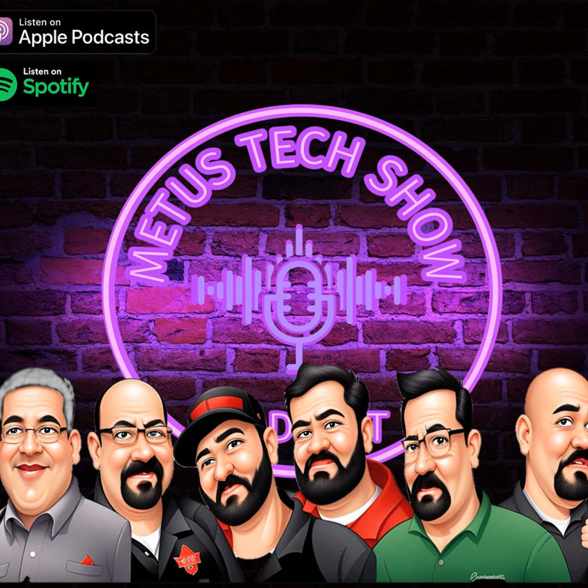Thanks, Paul. This week's METUS Minute is on solenoid valves. A solenoid valve is an electronically controlled device that acts as an on or off switch for refrigerant flow. They are crucial for controlling refrigerant flow in various stages of the HVAC cycle, including cooling, defrosting, and preventing refrigerant migration. A solenoid valve consists of a coil of wire, the solenoid, that when energized with electricity creates a magnetic field. This magnetic field attracts a movable core, either a plunger or an armature. The movement of the plunger opens and closes an orifice or port in the valve body, allowing or preventing fluid flow.